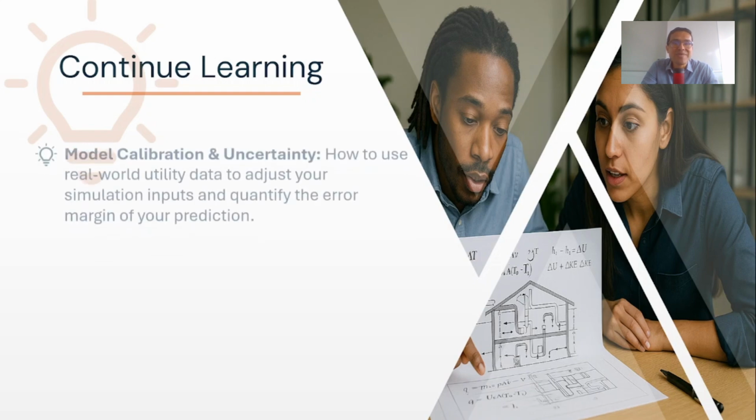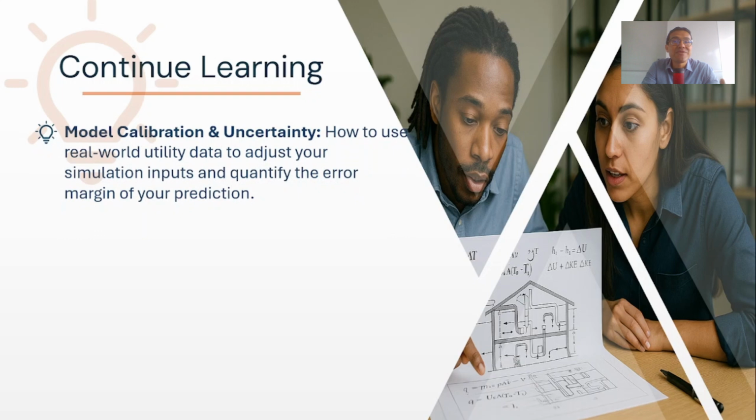We built a strong foundation today, but the field of BEM is always evolving. If you want to continue leveling up your skills, here are 3 advanced topics to explore. First, look into model calibration and uncertainty. It's one thing to build a model, but true experts know how to test it. Calibration is the process of using real-world utility data to tune your model's inputs, like schedules and infiltration, until the simulation results match the actual building's performance. You then quantify the prediction error to determine the model's reliability.